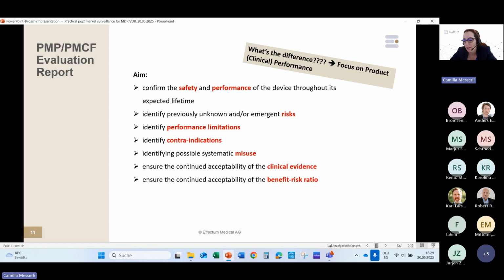For example, if you have a product that you already had on the market as a legacy device, and you have been marketing it, selling thousands of this product for years, and you have proof of its performance, then you can use this as a justification for why you don't need any further PMCF evaluations, because all the performance related information would be gathered through vigilance and CAPA review, and all that would be part of the PMS report.